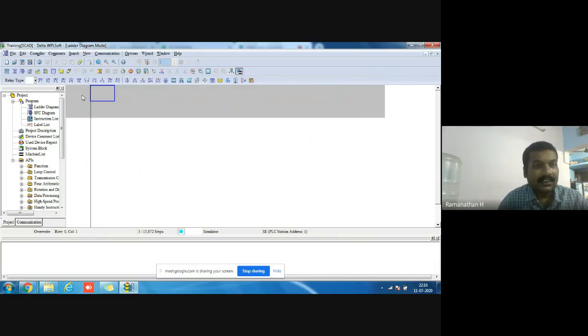If we have real hardware, we can work with it. Real hardware in the sense, suppose you have a chance to work with a real PLC model, you bring a potentiometer, a 10-volt potentiometer or a 4 to 20 milliamp potentiometer. That's only 20 to 30 rupees. You just connect it and vary the potentiometer, and the analog value will vary. I will tell how to assign the analog inputs.